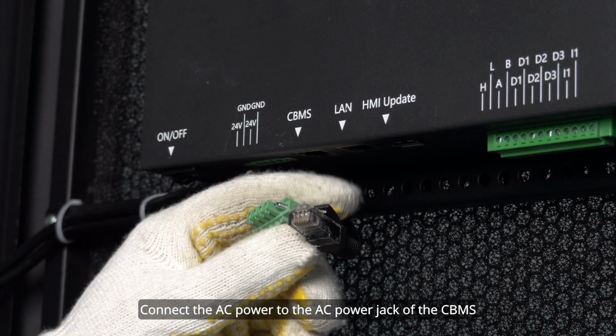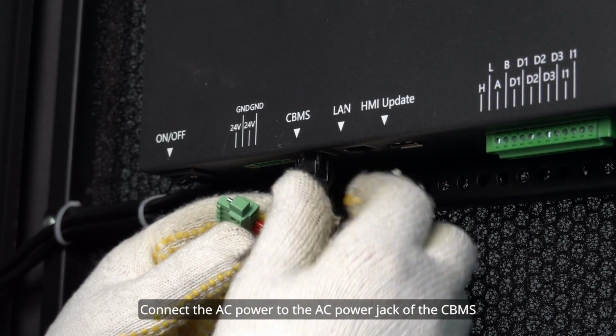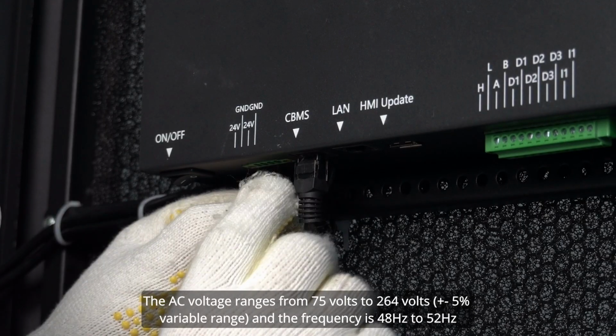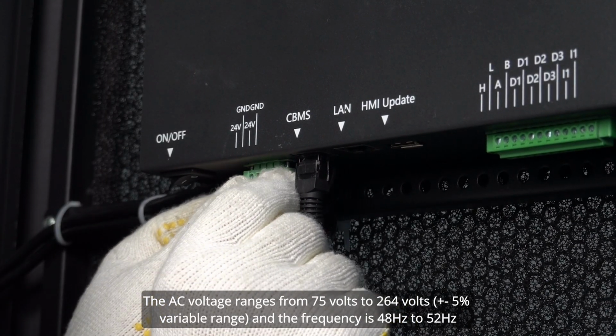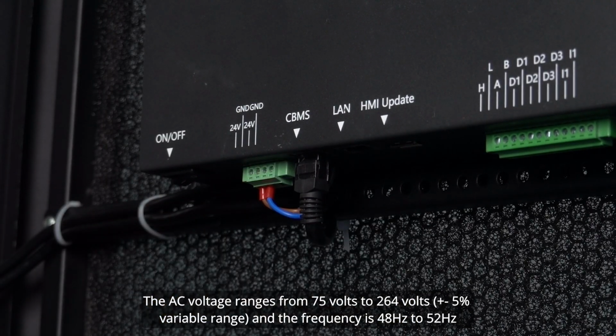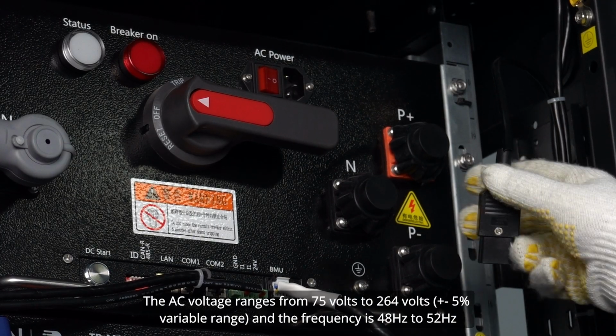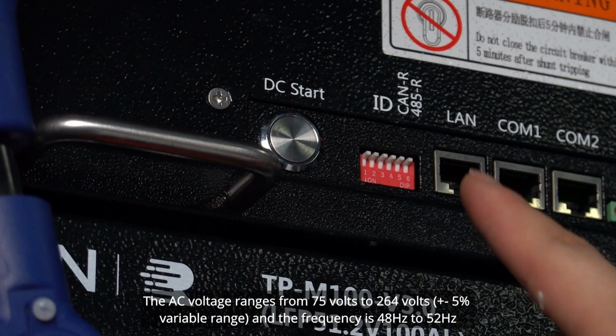Connect the AC power to the AC power jack of the CBMS. The AC voltage ranges from 75 volts to 264 volts, plus 5% variable range, and the frequency is 48 Hz to 52 Hz. Set the ID address of the CBMS according to the number of the parallel cabinets.